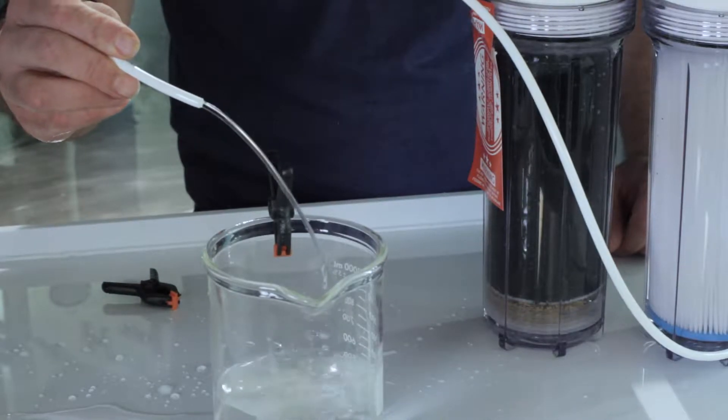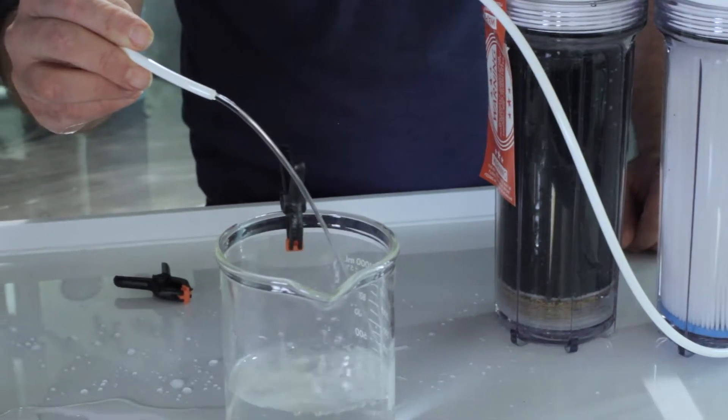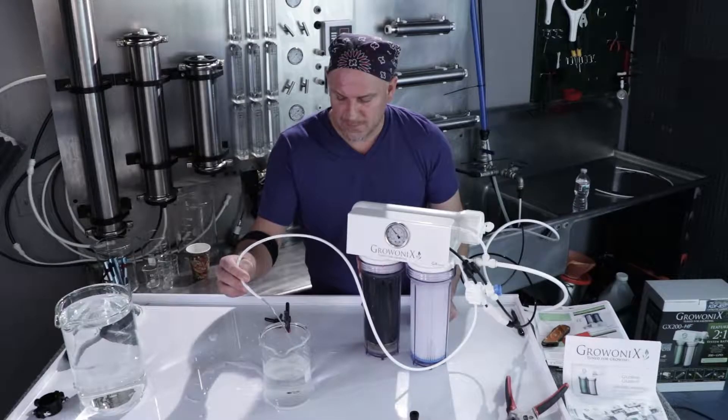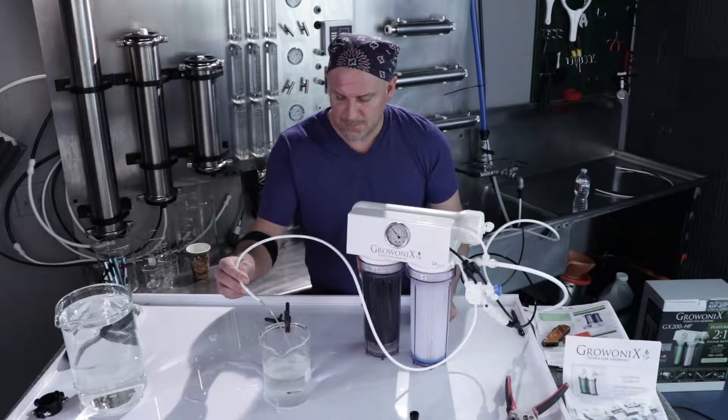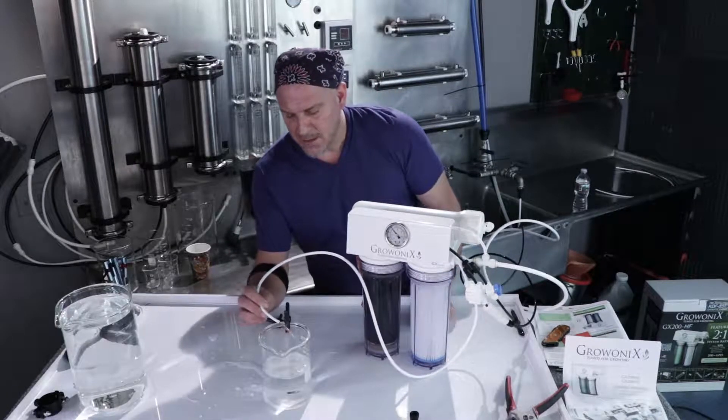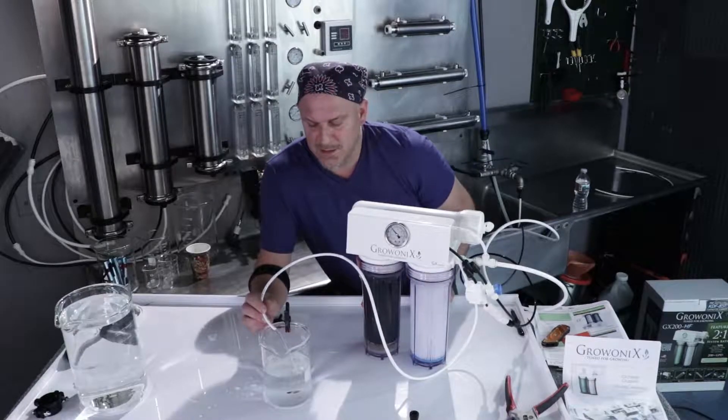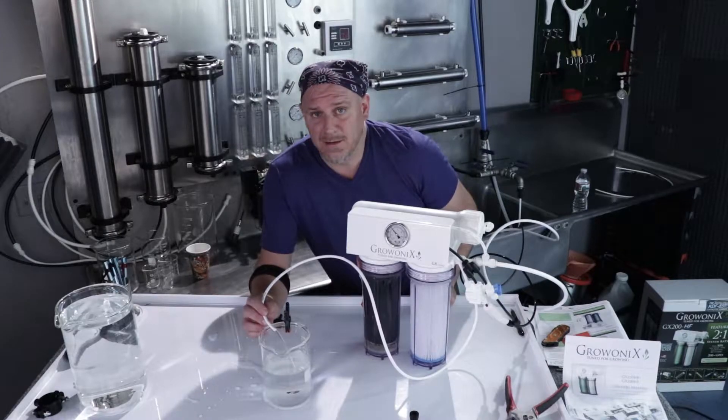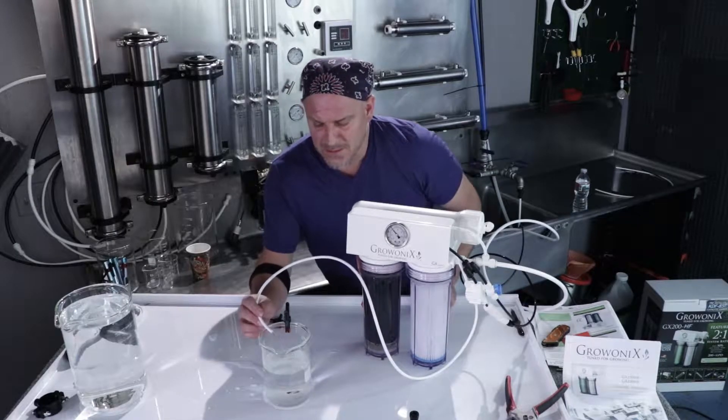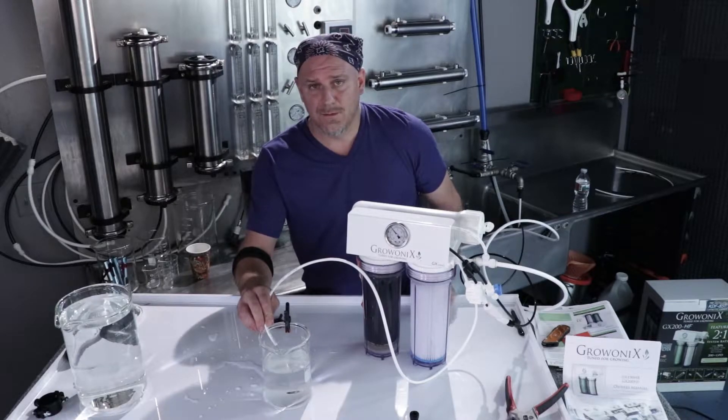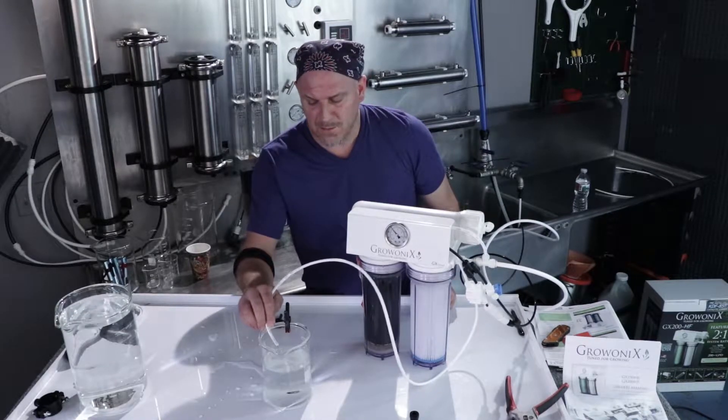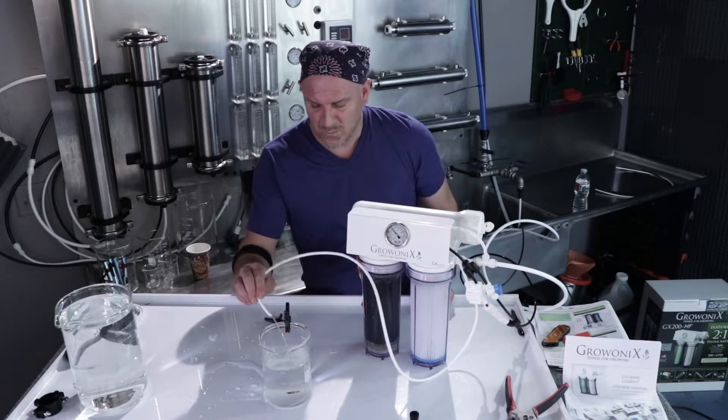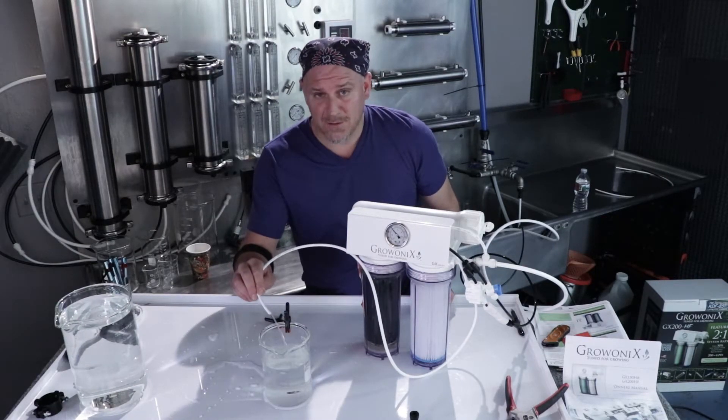You can still see the bubbles coming out of the permeate line because the permeate side of the membrane still needs a good flush. You'll also notice that on the first initial water that comes out, the TDS will be a little higher, and that's the storage solution. Membranes need to break in. They're scientific instruments. This membrane's really going to break in over the first few days of using it and flushing water through it. It's going to speed up production, the rejection's going to get better. And that's it for hooking up a GX200.